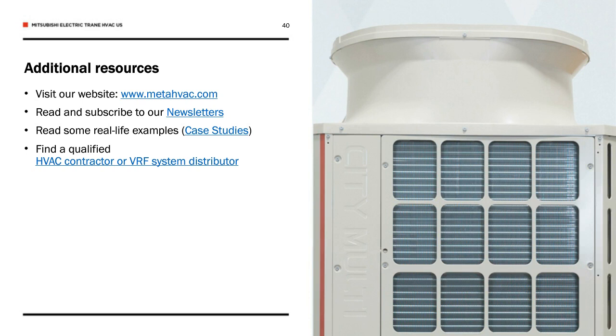Okay. So we have a few questions that have come in with regard to LEV kits. We'll start with one of the more basic ones. Can you give examples of where LEV kits, linear expansion valve kits, were used on existing equipment? Yeah, that's a simple but unique innovation that allows somebody to take an existing air handler, tie in a VRF condensing unit, and take advantage of the efficiencies that come with the inverter compressor without ripping out a whole bunch of other or ancillary equipment on the roof of a building or next to a building.